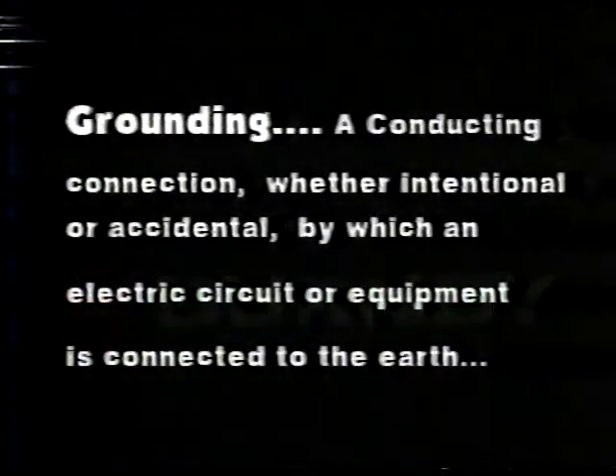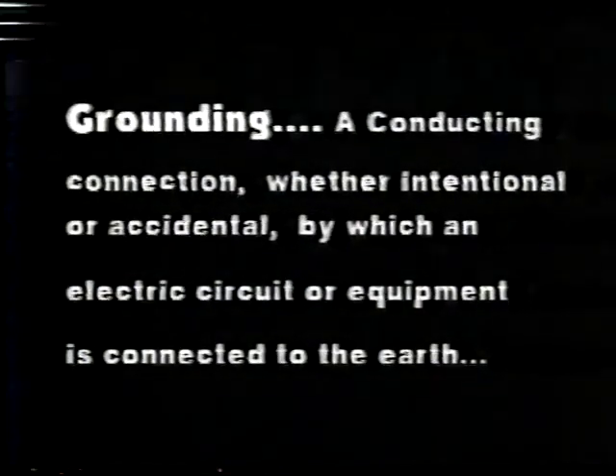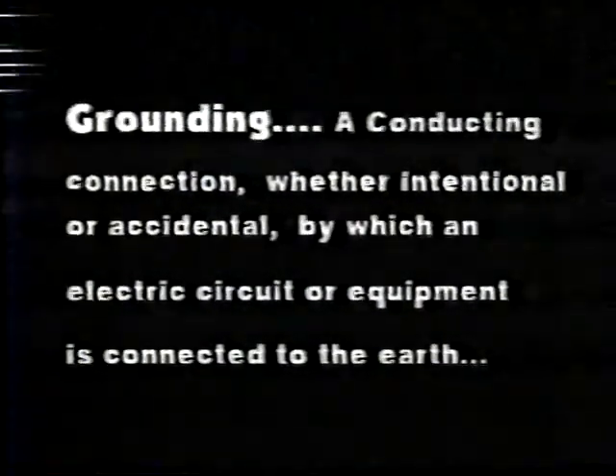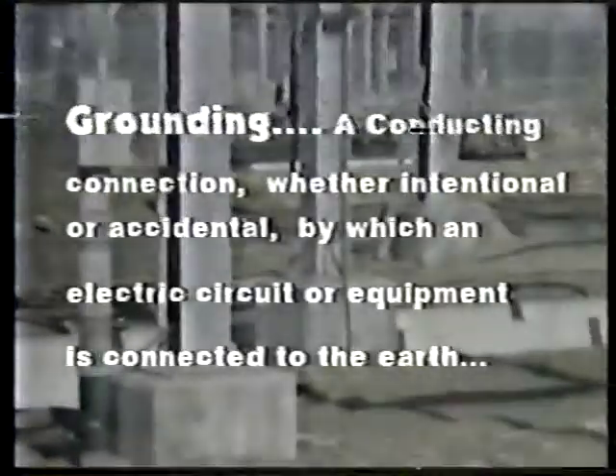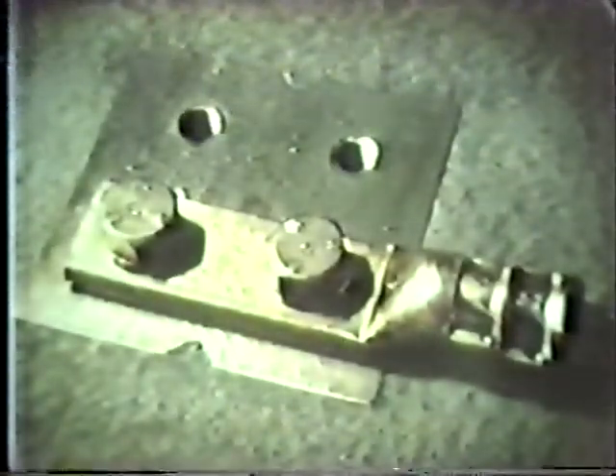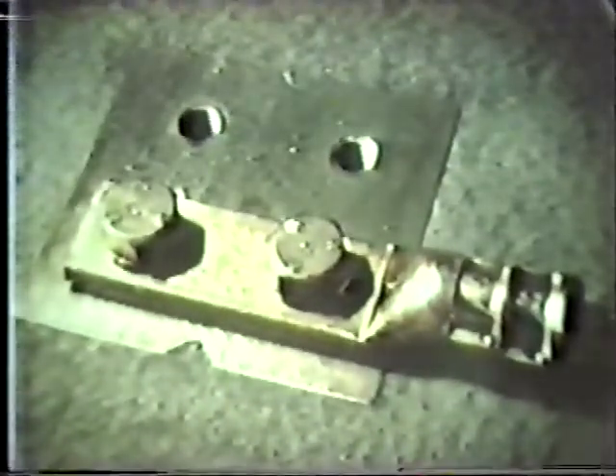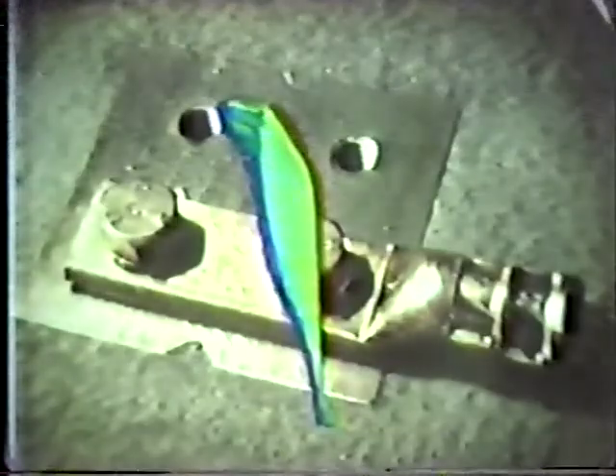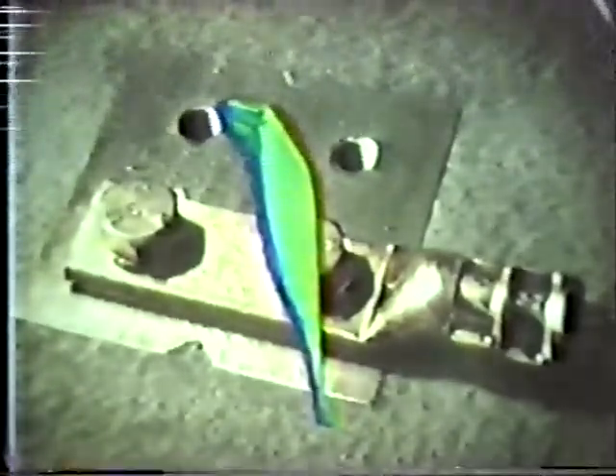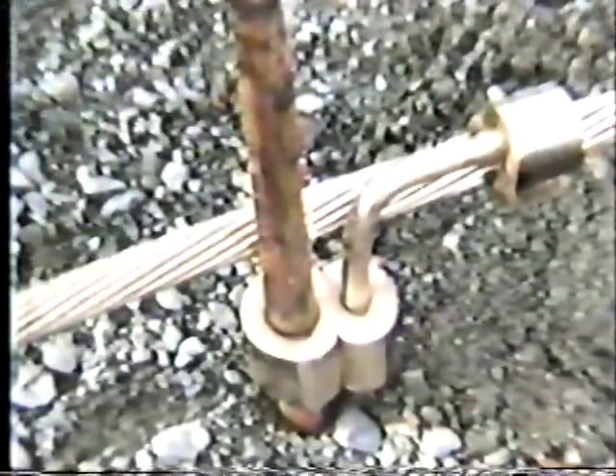Grounding: a conducting connection, whether intentional or accidental, by which an electric circuit or equipment is connected to the earth. Effective grounding is necessary to permit the proper and efficient operation of much of today's equipment. In many applications, the ground or grounding system may actually do nothing during normal operation. However, in the event of a malfunction or fault current, the grounding system provides the means to return the fault current safely to the earth.